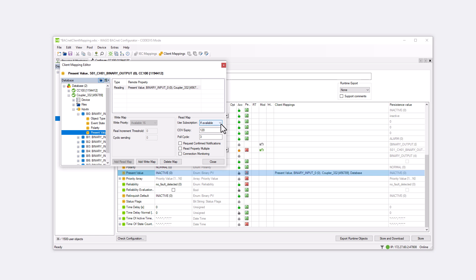The client's subscription to a property on the server expires after a defined period and must be requested again. This period can be specified at COV expiry. The default value is 120 seconds. After half the time, the client sends a new subscribed COV telegram. If this is not confirmed, the mapping expires after the set COV expiry time.